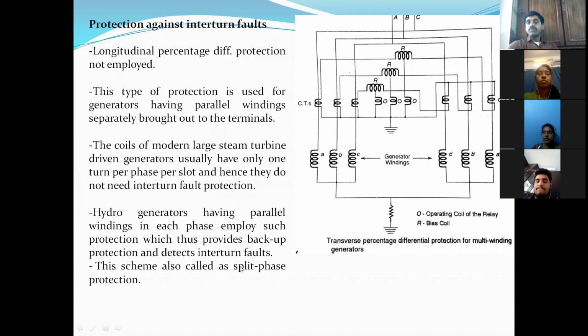This scheme is also called split phase protection. You can see here the generator windings, three phases A, B, C. Here there are two parallel connections. Here between the turns, the CTs are connected. These two CTs, and that means every phase CT is connected to the bias coil as well as the operating coil. Whenever there is a problem in the turns, the operating coil current will be more and the relay will operate. This is a transverse percentage differential protection. It is not longitudinal, it is transverse.